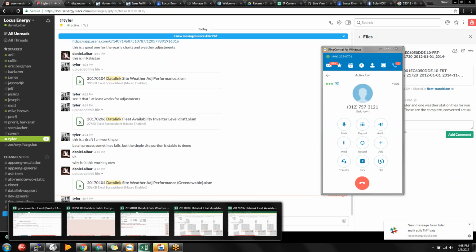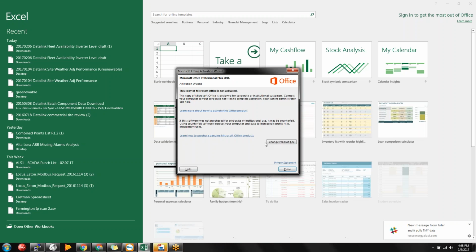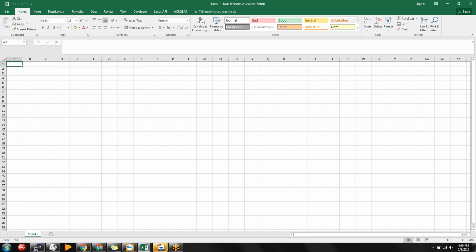Yep. All right, so it's actually not too hard, but it does take a visual aid. So a bit in a Modbus map will say, okay, bad, good. This is the fault. This is the bit. Let's say it's that simple. The bit will be starting at 0, usually going 1, 2, 3, and depending on the type of register, you can have a lot of bits, but let's just say we only have 3 bits for now. And this is the actual equivalent value of that bit. So it's actually 2 to the 0, which is 1. And if you copy that down, it'll be 2 and 4.